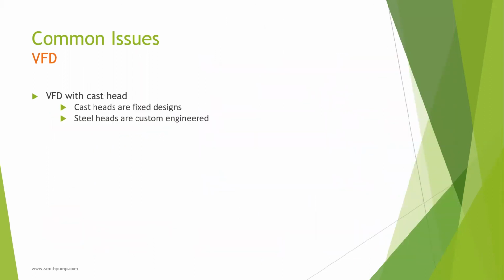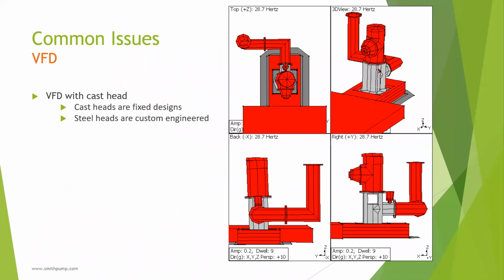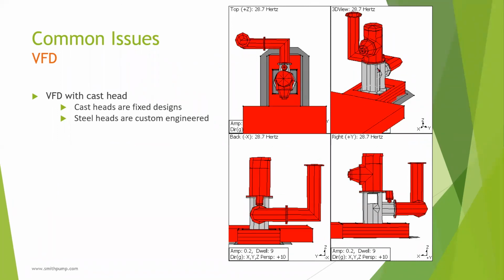Without getting deep into vibration analysis, vertical turbines have a good chance of operating at or near their natural frequency when running on a VFD. So what does that mean? Take a look at this animation. The pumps can start moving like this in real life. It's a great way to destroy the equipment and scare everyone at the job site.